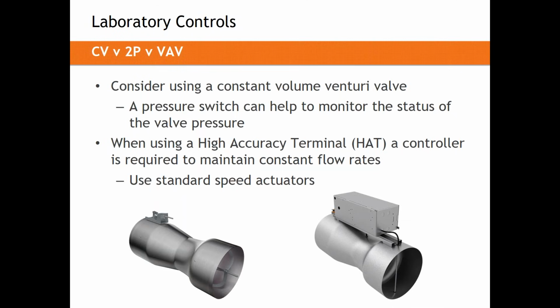One thing you should consider adding to that constant volume Venturi valve, however, is a pressure switch. The pressure switch will be an air proving switch. So basically, when your system sees the pressure switch contact closed, it knows airflow is present. And when it sees it open, it knows airflow is not present. So it's, do I have this airflow or not at all? It's a nice monitor for that system.